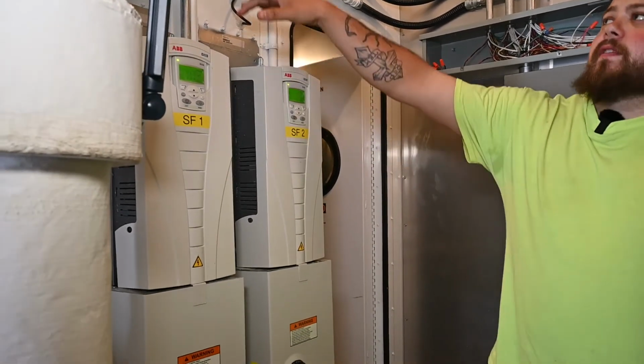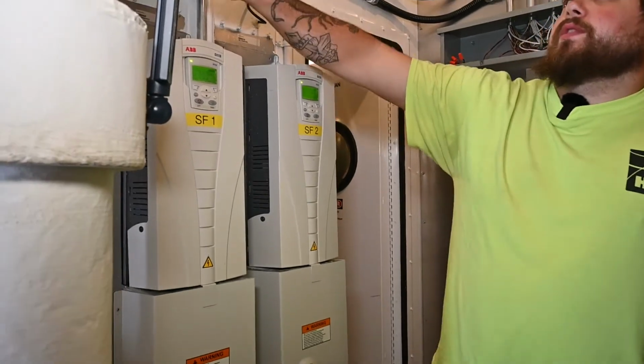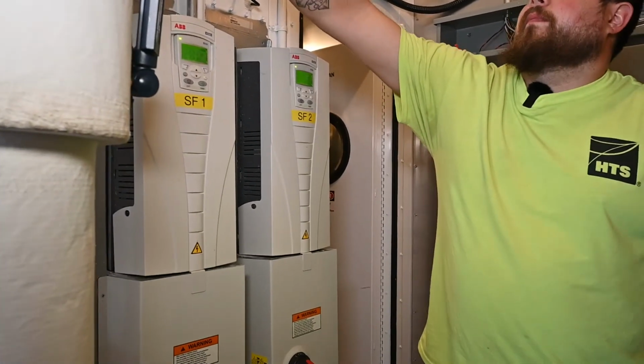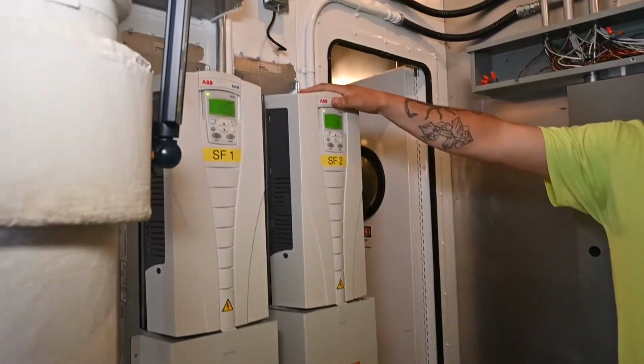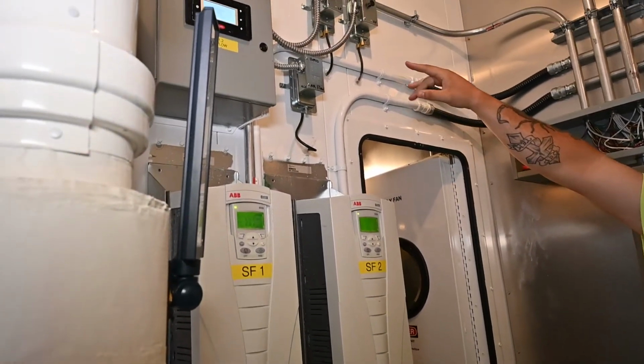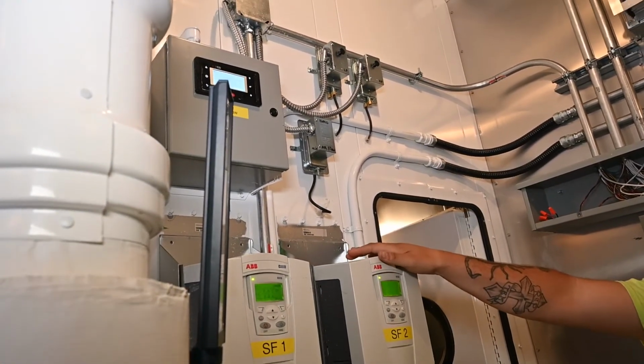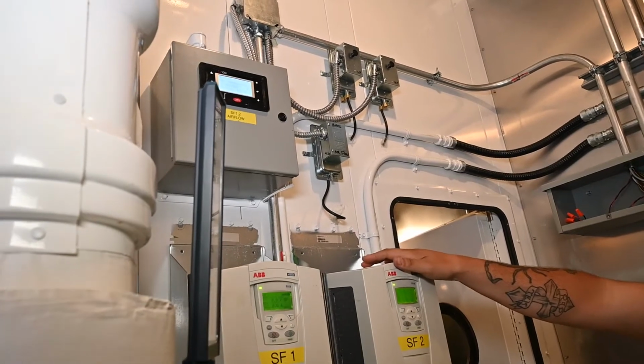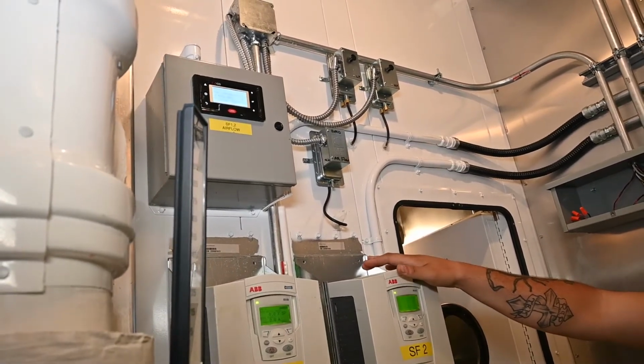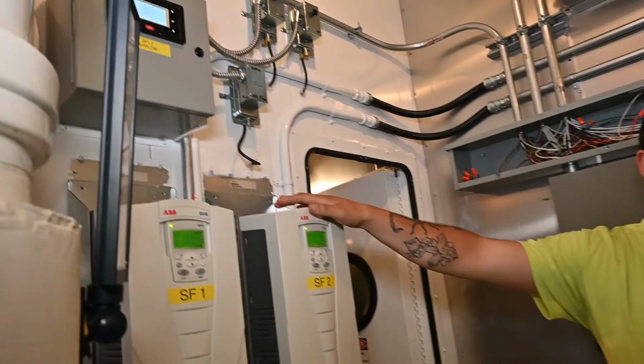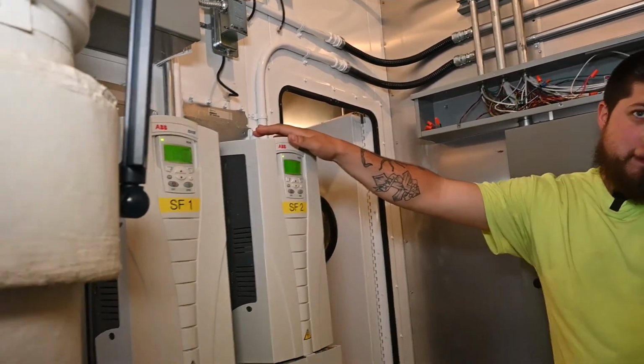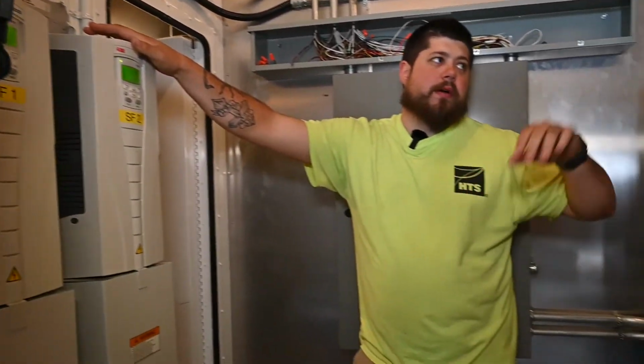Right above here is the airflow. It's a coil controller, just displays what you can see of the CFM of what's going on with each fan. Up here, Zenergy has low pressure, high pressure cutout switches. This is a safety, to shut down the fans if needed. We also have a main disconnect right here to the other side of the wall, which kills power to everything past this disconnect, to the VFDs, to the motor.